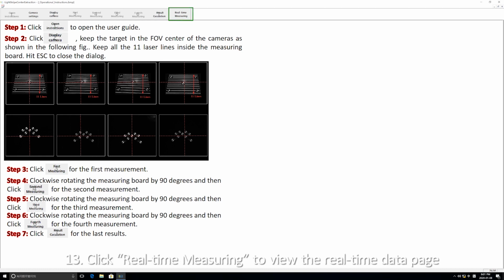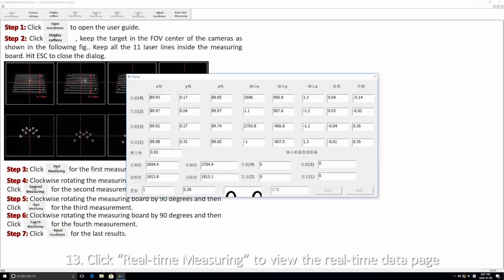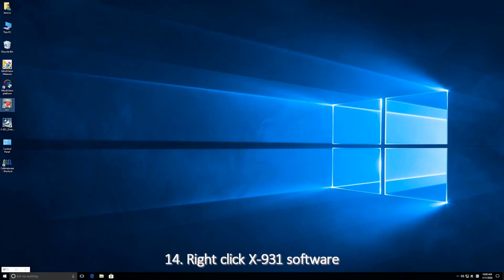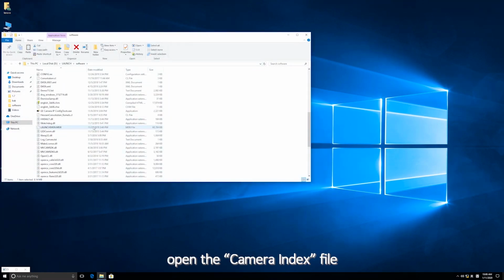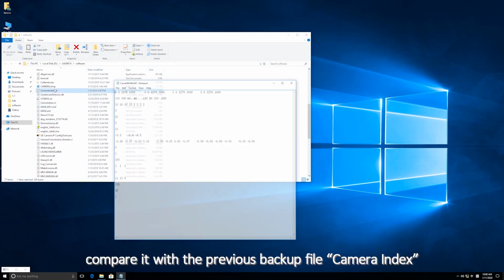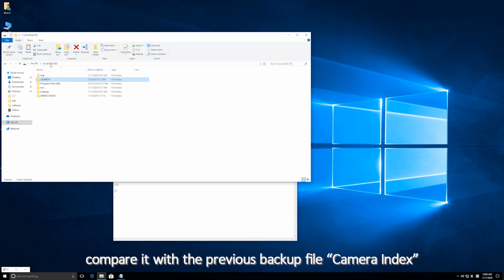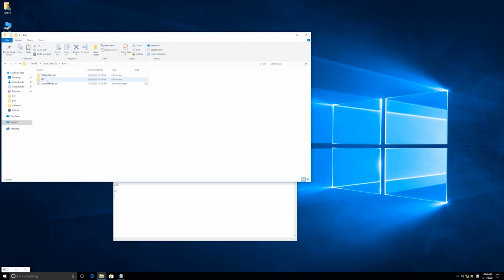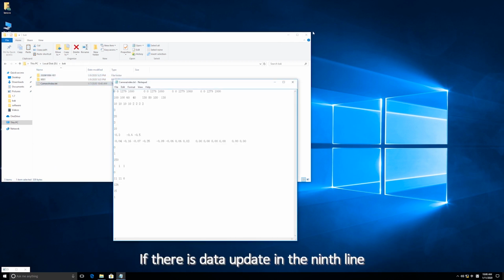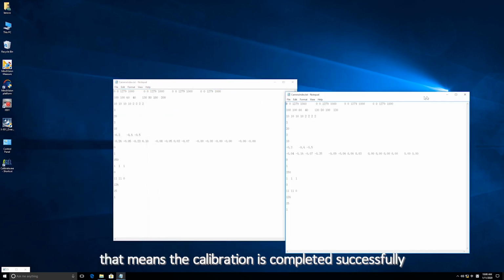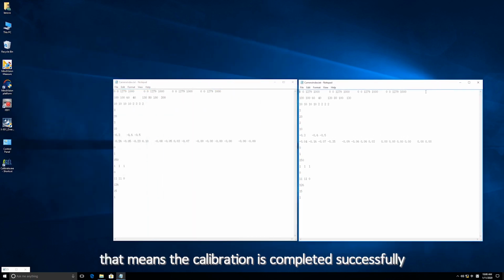13. Click Real-Time Measuring to view the real-time data page. Click X on the top right corner to exit the software. 14. Right-click X-931 software, open the camera index file, and compare it with the previous backup file, camera index. If there is a data update in the 9th line, that means the calibration is completed successfully.